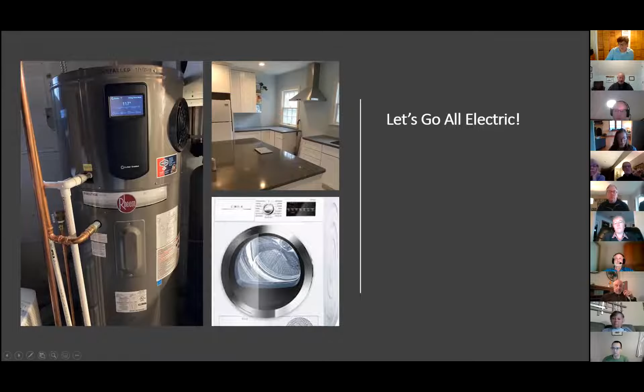So we started with a Manual J calculation and determined our house was going to be right around 42,000 BTUs. We know Manual J's tend to be a little conservative, so we figured we could undersize the heat pump slightly and use resistance backup heat.